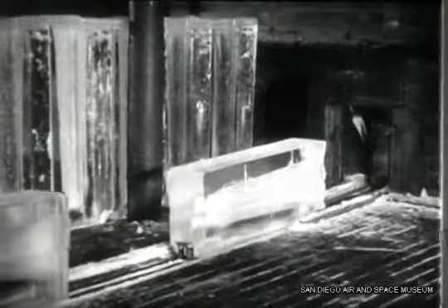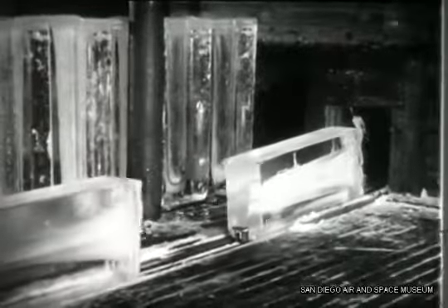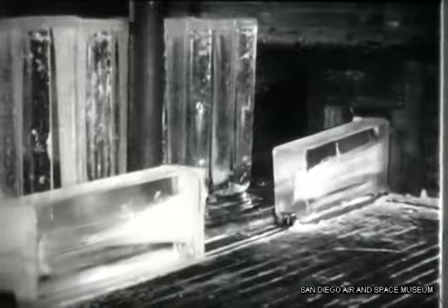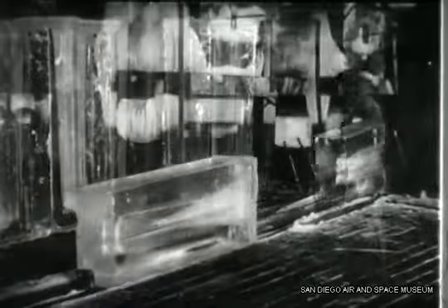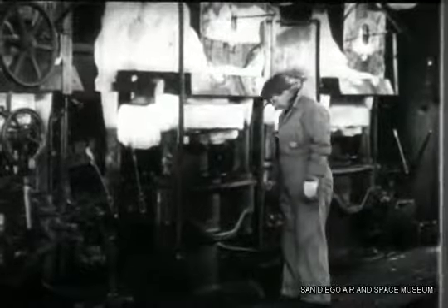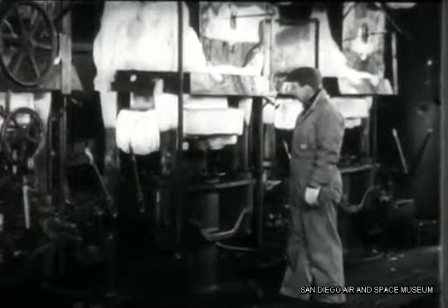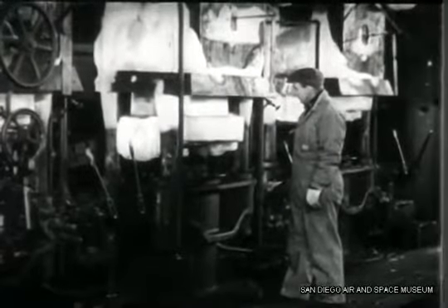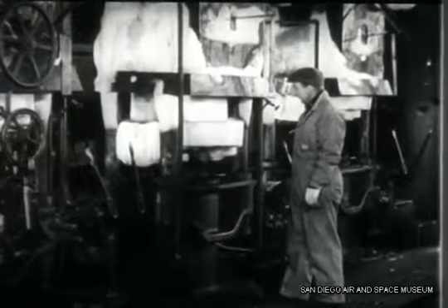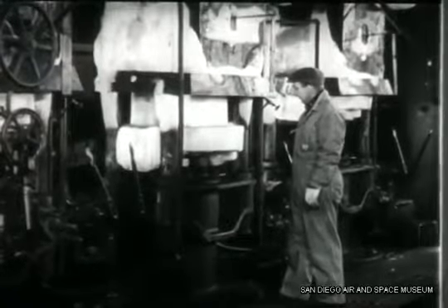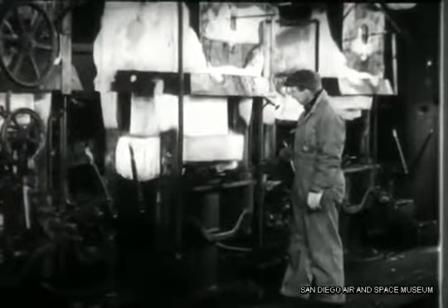But it isn't considered suitable for Navy use because its fumes are irritating and it is slightly inflammable. Carbon dioxide is a good refrigerant too, also used in industrial systems. But chiefly because of the tremendous size and weight of the equipment needed to handle its high pressures, it isn't used in modern Navy systems.